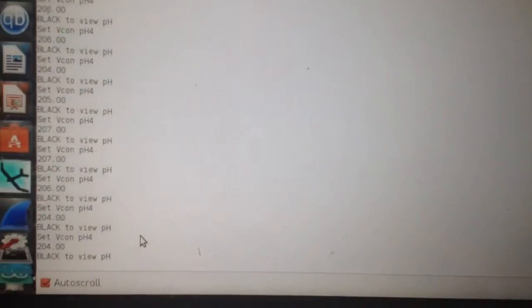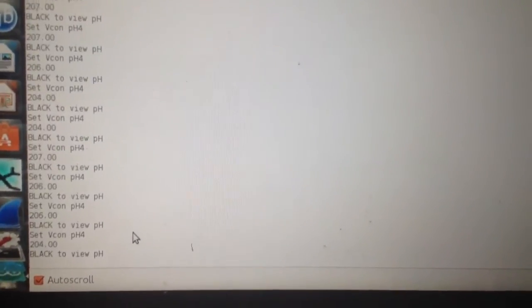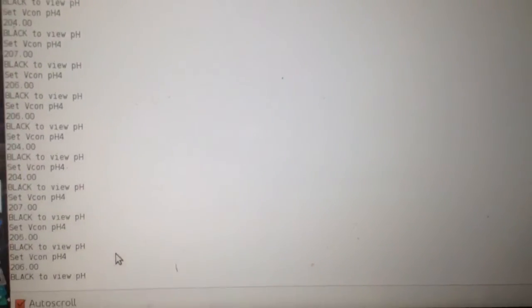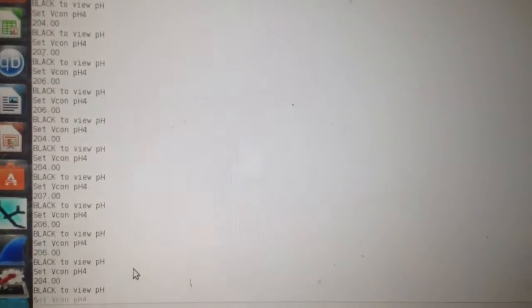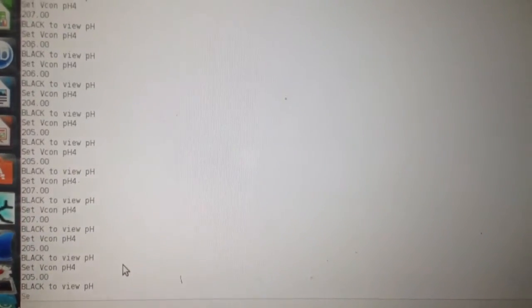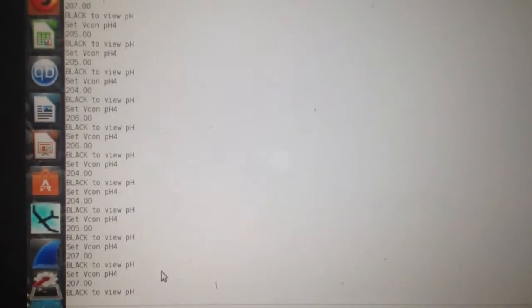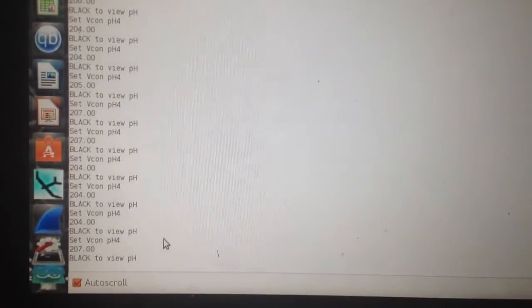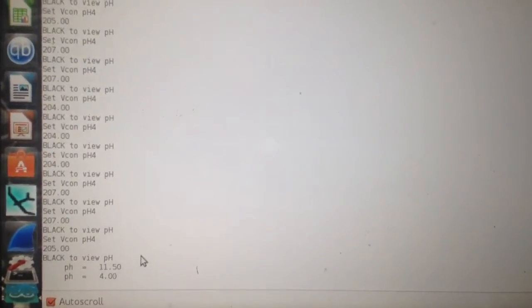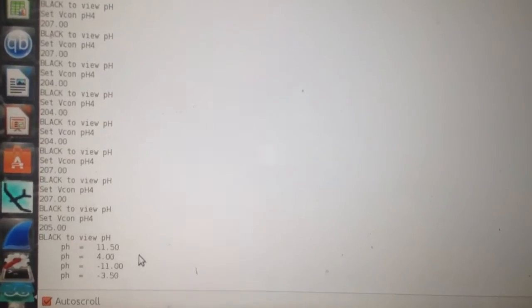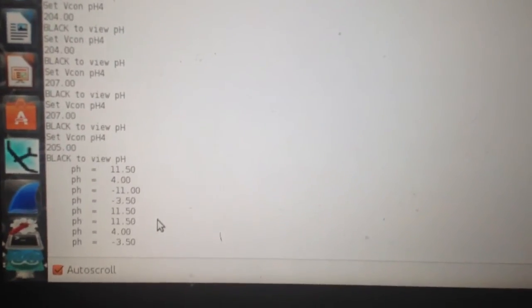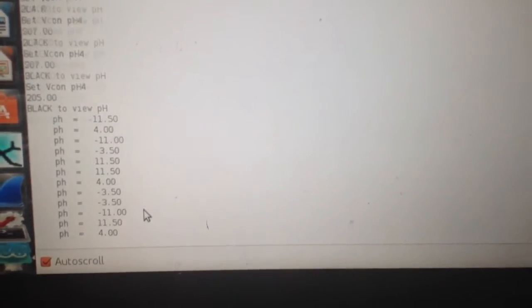Alpha is your constant. In the equation, alpha is a constant that is acquired by pressing the red button. When you press the red button, it sets that constant, and then it uses the live signal to calculate pH. Then you can go to the next button, and it'll actually display all the pHs.